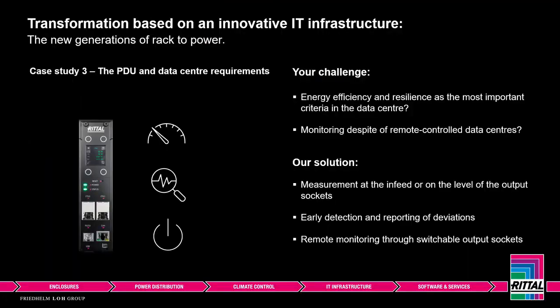As an option, a residual current measurement can also be integrated into the PDU. This can replace a regular insulation test, which increases the availability of a data center. In addition, safety is increased because residual current can also be detected and localized at an early stage.